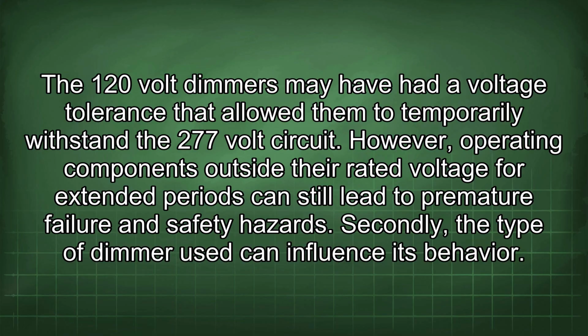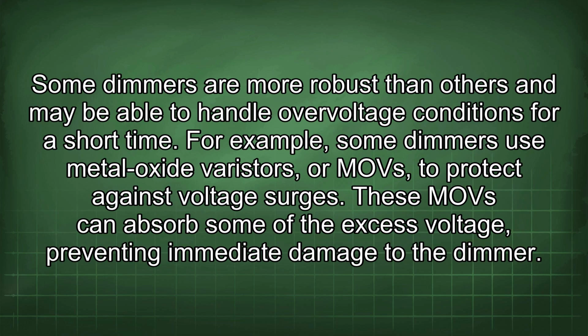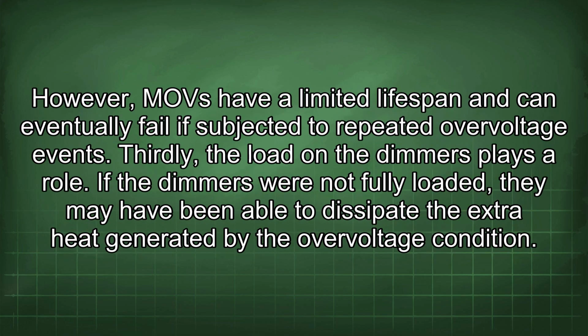Secondly, the type of dimmer used can influence its behavior. Some dimmers are more robust than others and may be able to handle overvoltage conditions for a short time. For example, some dimmers use metal oxide varistors or MOVs to protect against voltage surges. These MOVs can absorb some of the excess voltage, preventing immediate damage to the dimmer. However, MOVs have a limited lifespan and can eventually fail if subjected to repeated overvoltage events.